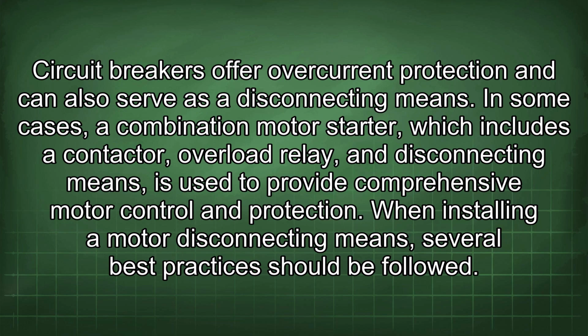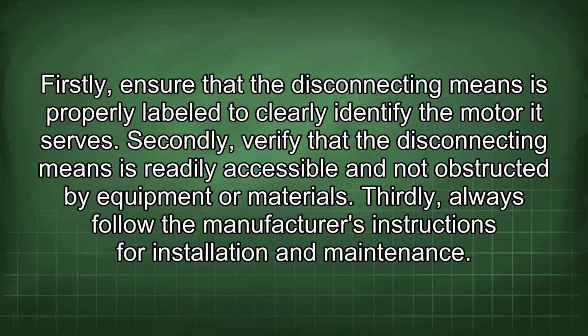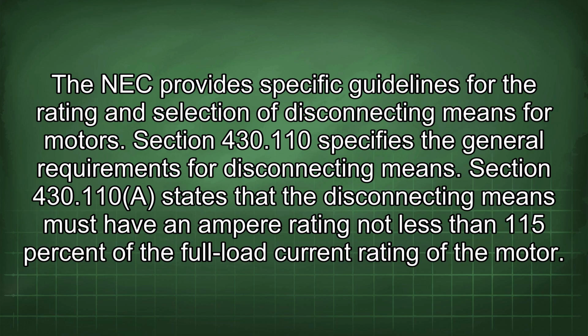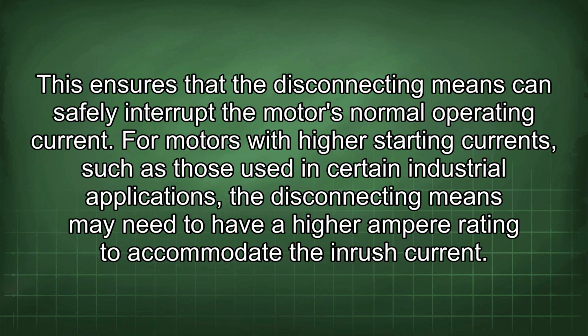When installing a motor disconnecting means, several best practices should be followed. Firstly, ensure that the disconnecting means is properly labeled to clearly identify the motor it serves. Secondly, verify that the disconnecting means is readily accessible and not obstructed by equipment or materials. Thirdly, always follow the manufacturer's instructions for installation and maintenance. The NEC provides specific guidelines for the rating and selection of disconnecting means for motors. Section 430.110 specifies the general requirements for disconnecting means. Section 430.110 states that the disconnecting means must have an ampere rating not less than 115% of the full load current rating of the motor. This ensures that the disconnecting means can safely interrupt the motor's normal operating current.